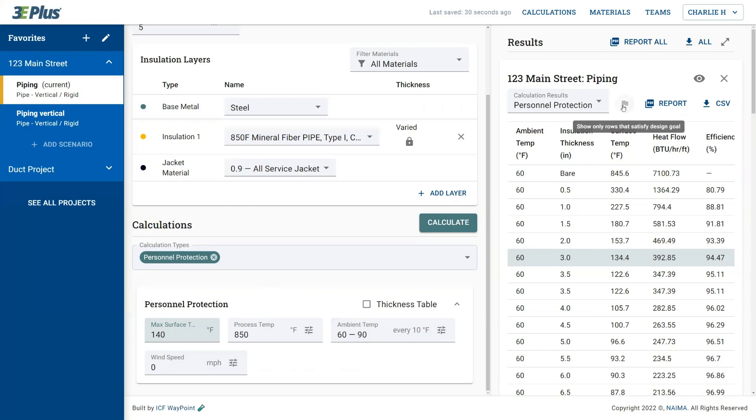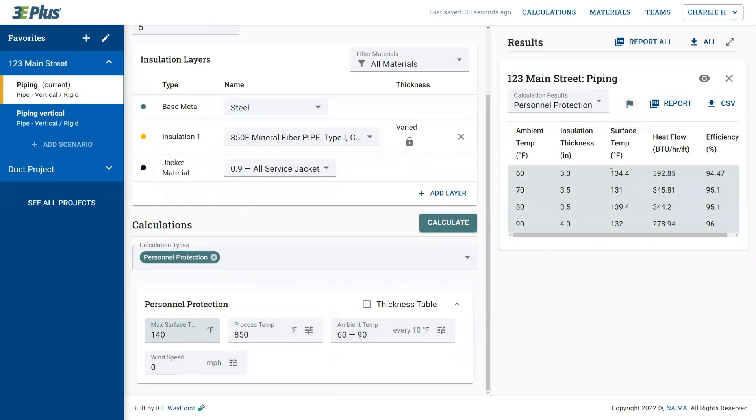You can click the flag icon to show only rows that satisfy the design goal. So in this case, it gives you those four answers for each of those ambient temperatures that were run. That's the amount of insulation you'd need to ensure personnel protection on that pipe.